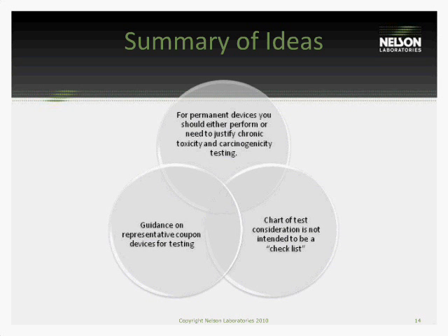The next one is guidance on representative coupon devices. And I love this one. Many devices are very, very small or very expensive to manufacture. And for biocompatibility, we only care about materials and processing. We don't need to test a functional device. So we have guidance now in this document on how to develop coupons or representative testing devices. These testing devices represent the same material in the same proportions as your final device, and the same processing is represented.